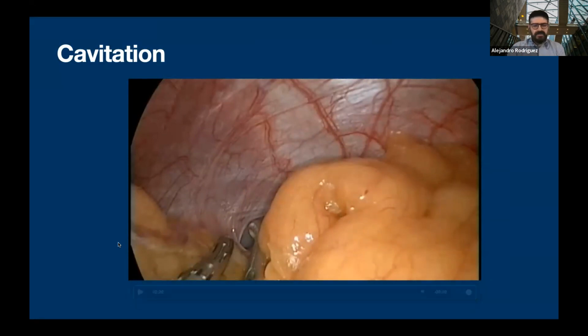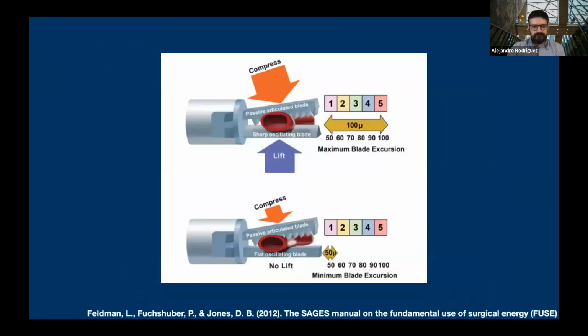One big point that Tom touched on with ultrasonic devices is that this lower jaw will stay hot for a good few seconds after you stop activating it — at least six seconds — and it can actually injure the tissue it touches. That's one big thing you have to keep in mind when using this device.